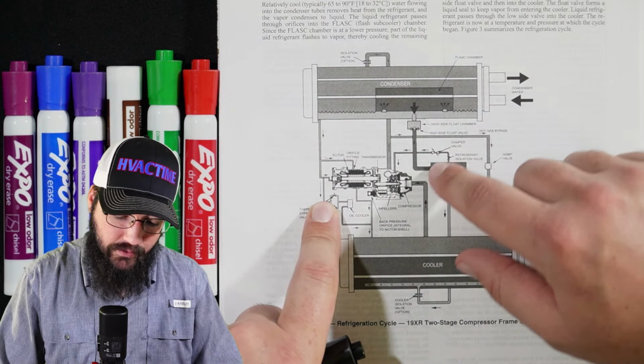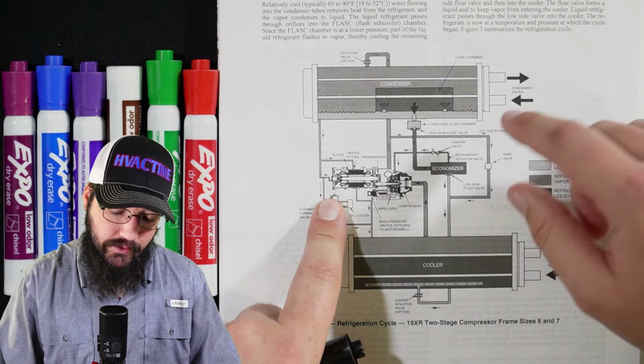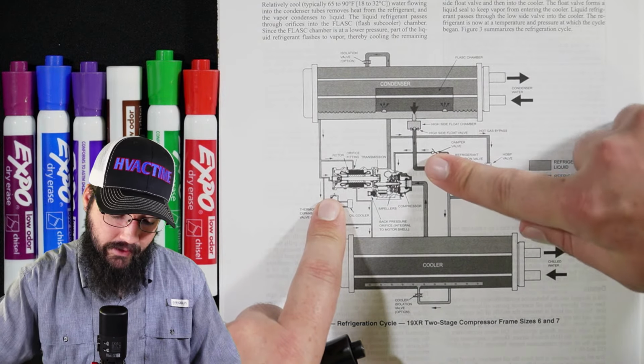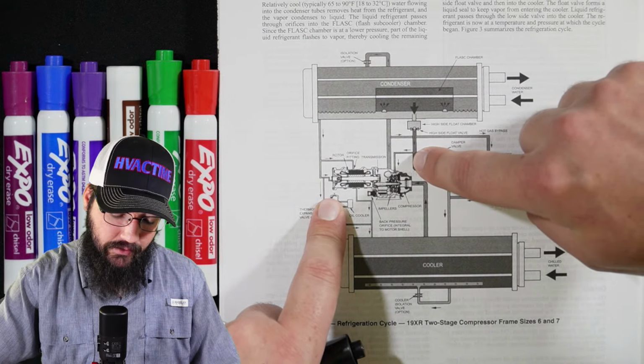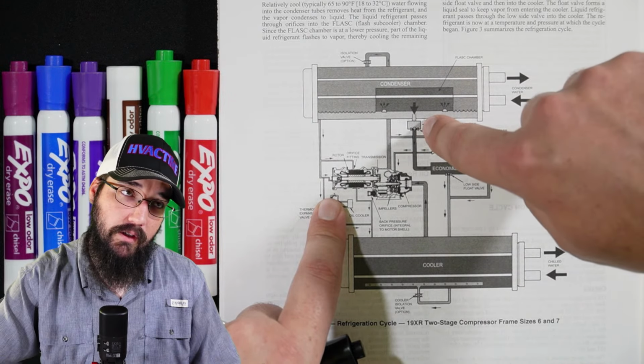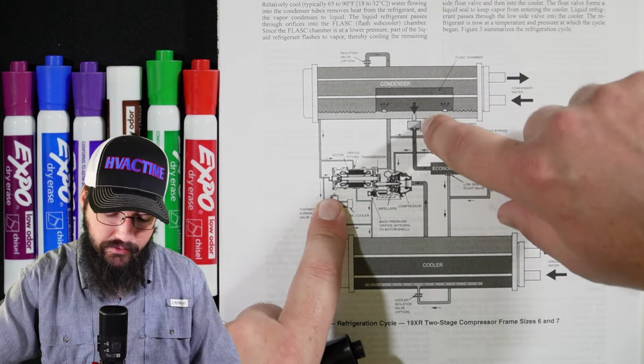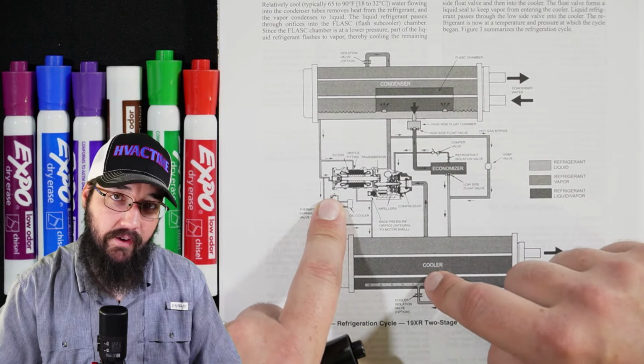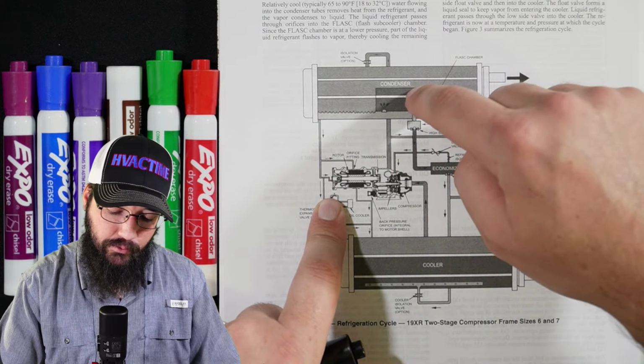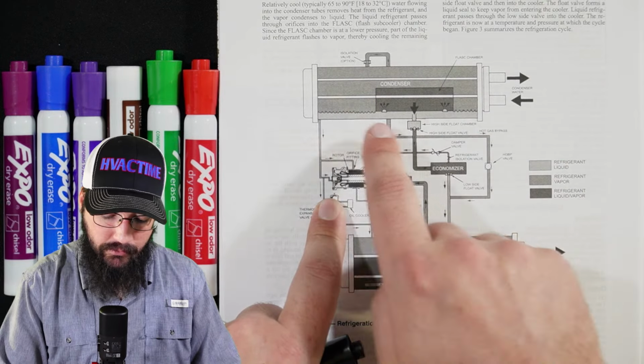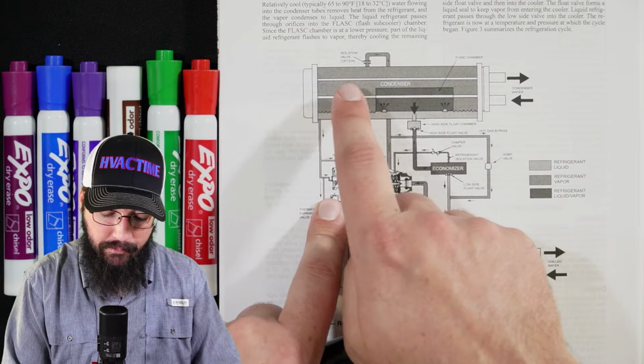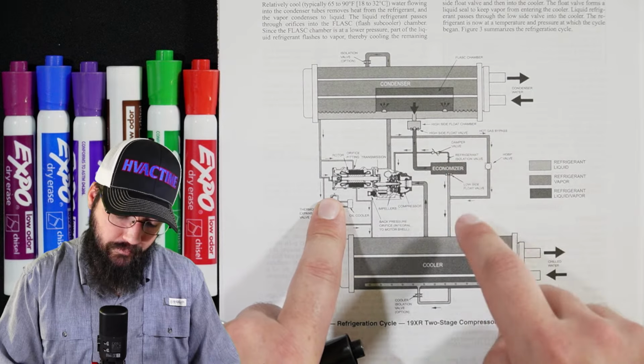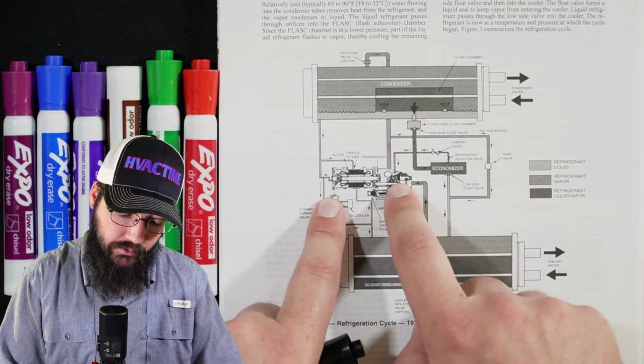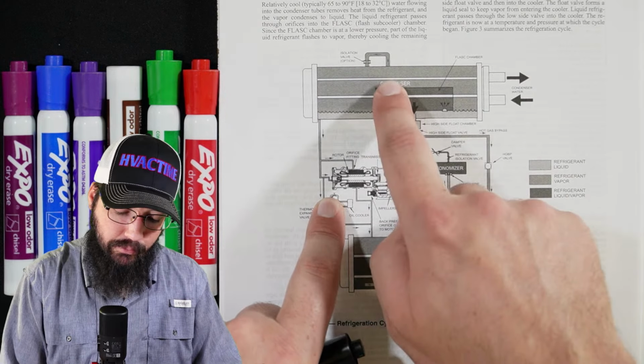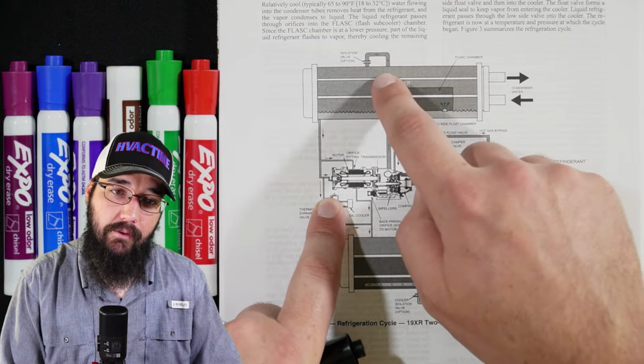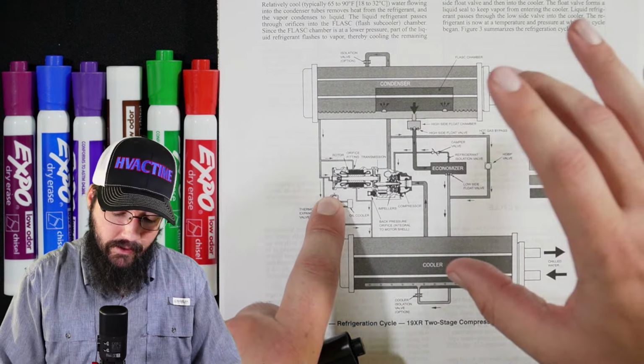Like I said, if this wasn't a two-stage compressor, if it was a single stage, then we wouldn't have any of this, and we would just come straight out of the float valve and then directly into our evaporator and go from high pressure to medium pressure to low pressure. But in this case, with the two-stage economizer, we go from high pressure to medium high to medium low to low pressure. Then we draw back into the compressor, and then we compress that back up to a high pressure, and the cycle repeats. Okay, that is the core function.